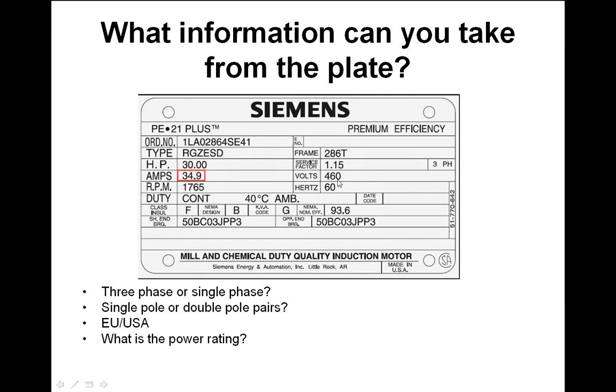Three-phase is confirmed by the voltage reading. Single or double pole pairs can be worked out from the RPM. If running at 60 Hz, synchronous frequency should be 3600 RPM. This motor shows 1765 RPM — should be 1800 for a double pole pair asynchronous motor, but it's slipping behind synchronous speed as expected. So it's confirmed as a double pole pair asynchronous motor made for the USA.